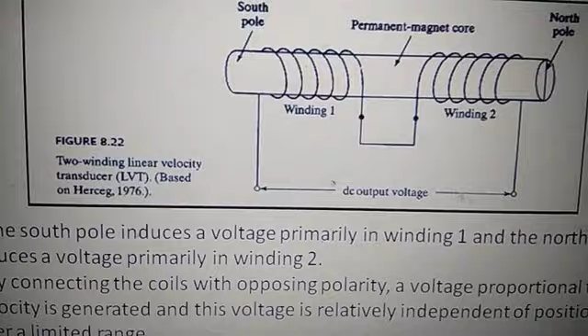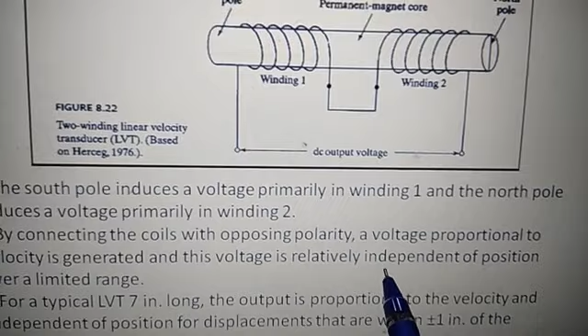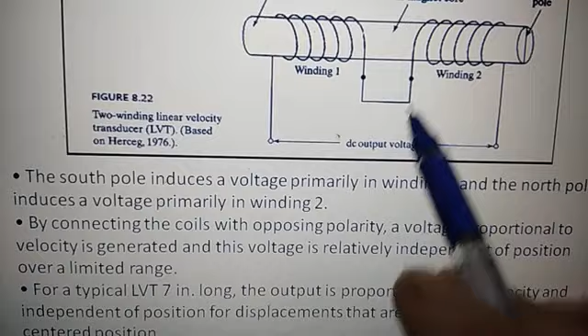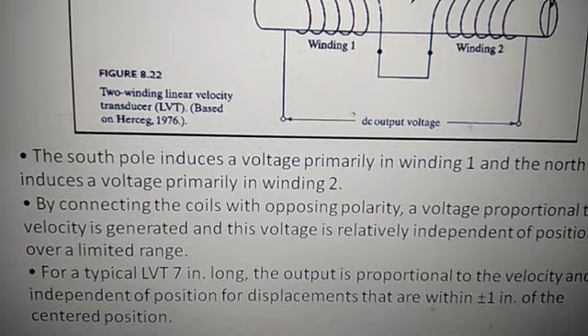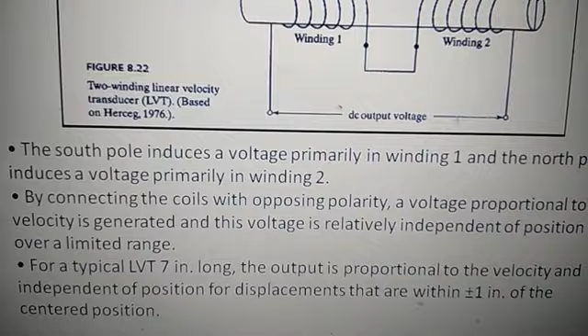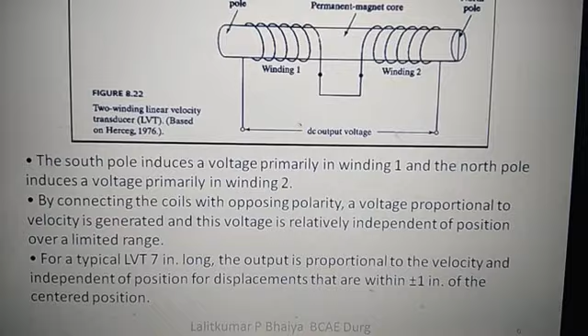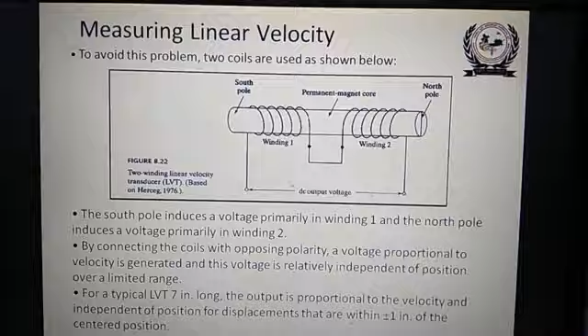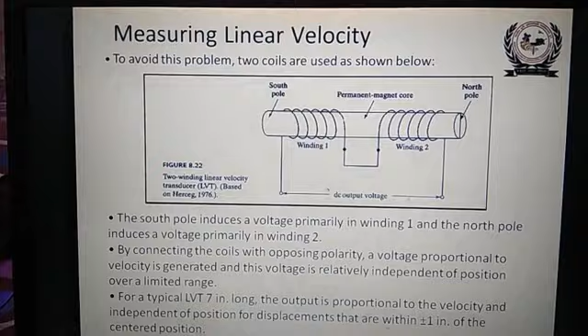The south pole induces a voltage primarily in winding 1, and the north pole induces a voltage primarily in winding 2. So here north pole induces the voltage, here south pole induces the voltage. By connecting the coils with opposing polarity, a voltage proportional to velocity is generated, and this voltage is relatively independent of the position over a limited range. Here you will get the proportional voltage. So for a typical LVT, the output is proportional to the velocity and independent of position for displacements that are within plus or minus 1 inch of the centered position. This is the dimensions of how to use this velocity meter, linear velocity.